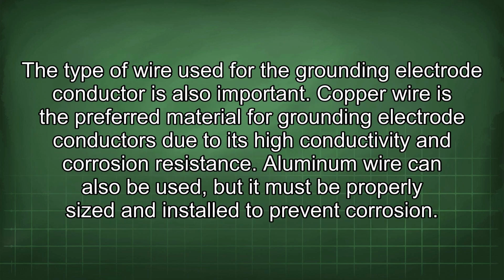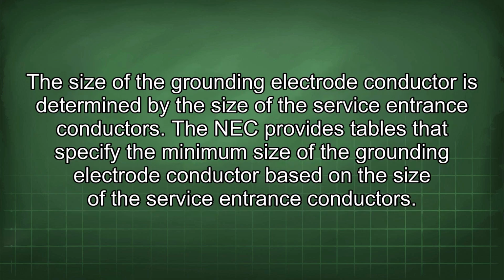The type of wire used for the grounding electrode conductor is also important. Copper wire is the preferred material for grounding electrode conductors due to its high conductivity and corrosion resistance. Aluminum wire can also be used, but it must be properly sized and installed to prevent corrosion. The size of the grounding electrode conductor is determined by the size of the service entrance conductors.